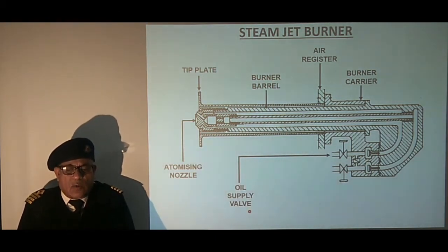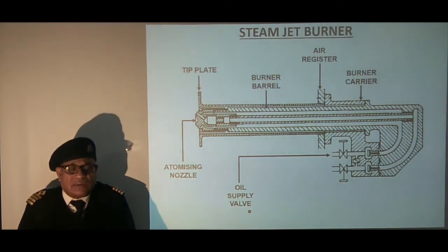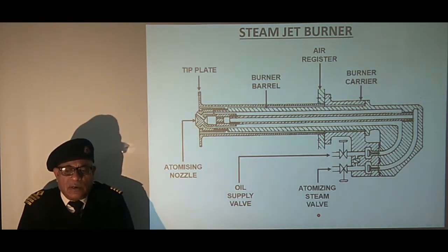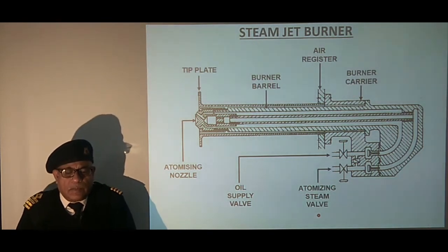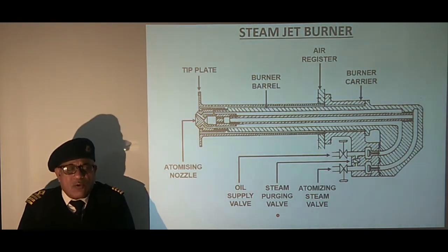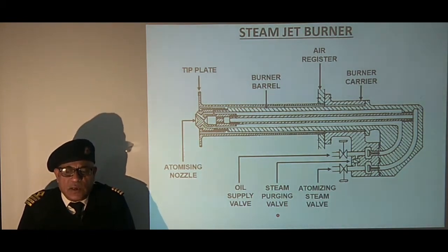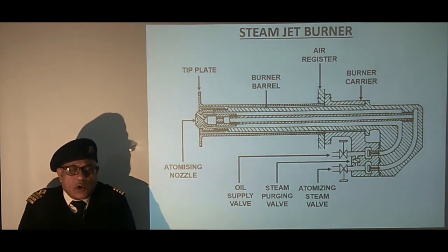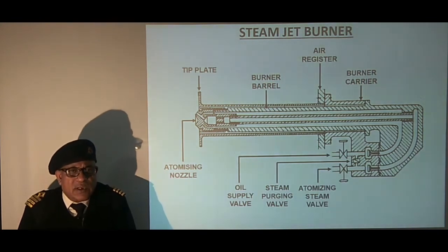Oil is supplied to the outer channel of the barrel through quick shutoff and check valves. Atomizing steam is supplied to the inner channel of the barrel through quick shutoff and check valves. A steam purging valve is provided to drive out remaining oil in the barrel when the burner is stopped. This prevents any tendency of the remaining oil freezing, which becomes highly viscous after cooling down.